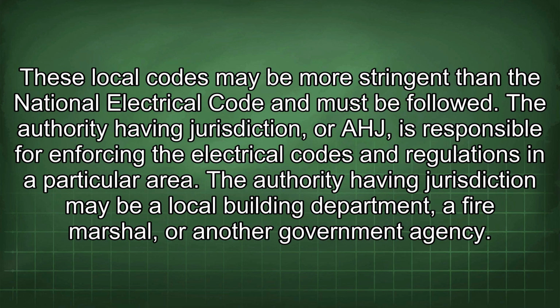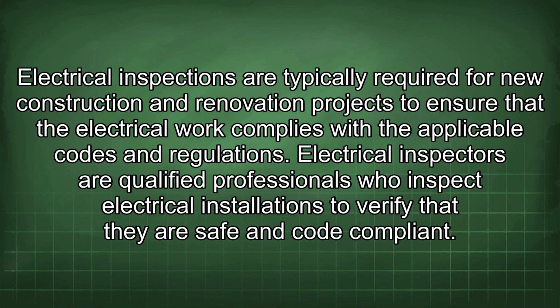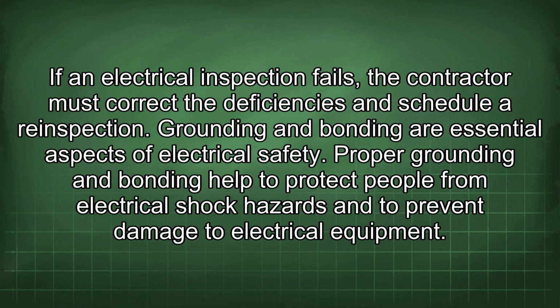The authority having jurisdiction, or AHJ, is responsible for enforcing the electrical codes and regulations in a particular area. The authority having jurisdiction may be a local building department, a fire marshal, or another government agency. Electrical inspections are typically required for new construction and renovation projects to ensure that the electrical work complies with the applicable codes and regulations. Electrical inspectors are qualified professionals who inspect electrical installations to verify that they are safe and code compliant. If an electrical inspection fails, the contractor must correct the deficiencies and schedule a re-inspection.